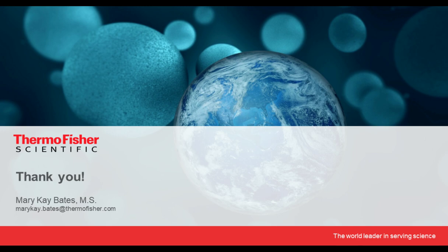And there are companies that will come in and do a manual chemical disinfection on your incubator, and many of those are good. Make sure that it won't corrode or cause degradation of the electronics in your incubator, and make sure that company is going to verify neutralization of the chemical that they use and document the efficacy in the end, that they truly did sterilize your system.